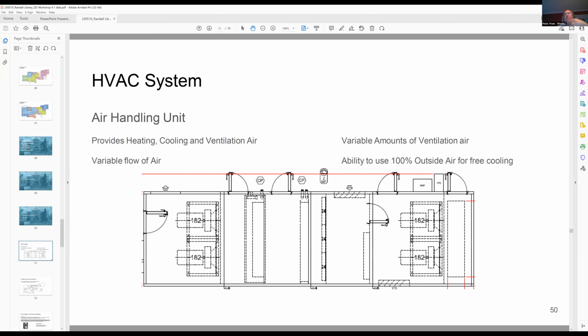We also vary the amount of ventilation air into the space. That's important because ventilation air, or outside air, is extremely expensive to condition. By reducing that amount of air from a code minimum to a maximum of your maximum occupancy, we can save energy by not using that outside air. We've implemented a strategy called demand control ventilation. It senses how many people are in the space, how many gases are off-gassing from the folks, and it'll bring in the amount of outside air that is required to keep people comfortable.